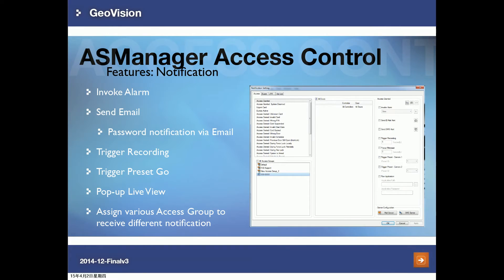AS Manager can send notifications when an event happens, such as invoking an alarm or a PC alarm, and can also send email notifications. You can trigger recording when an event happens, or trigger a PTZ camera preset — for example, having a PTZ camera point to a reader when a card is swiped. You can also pop up a live camera view, and assign different access groups to receive different notifications for different events.